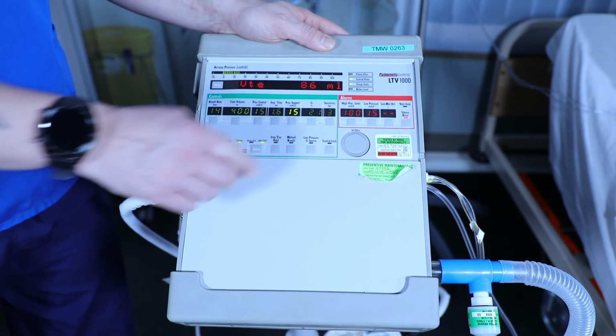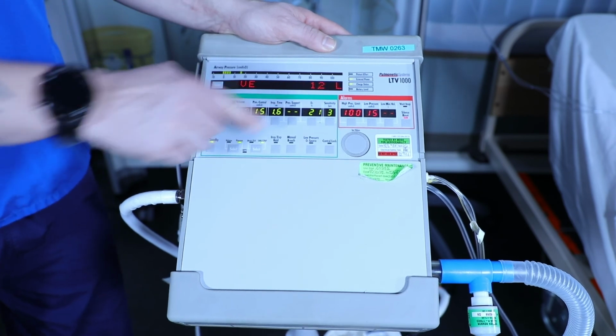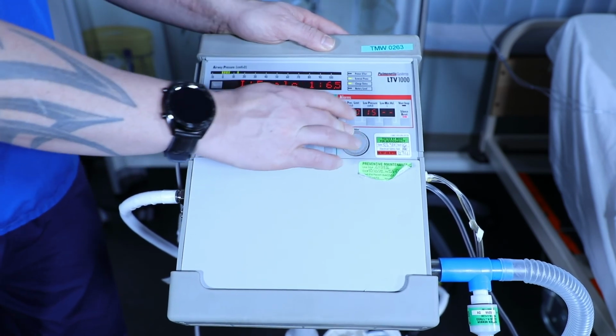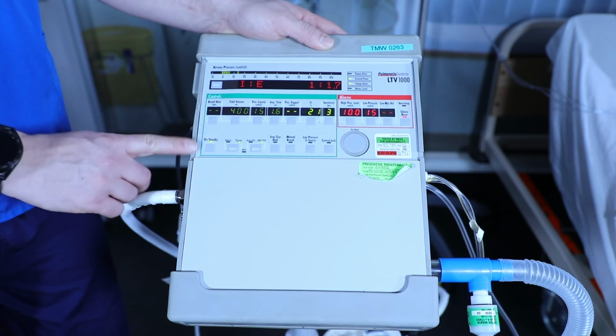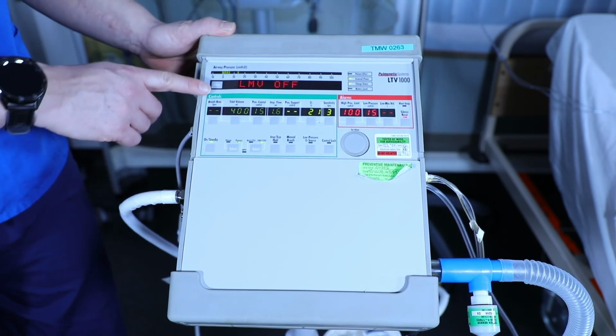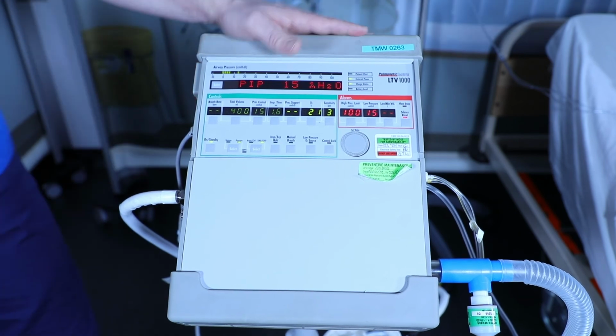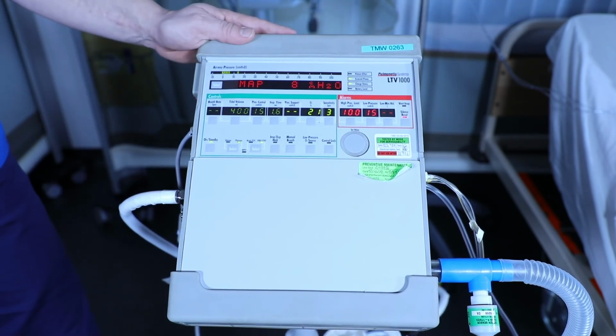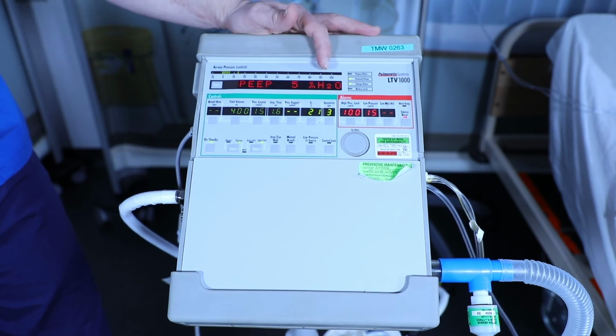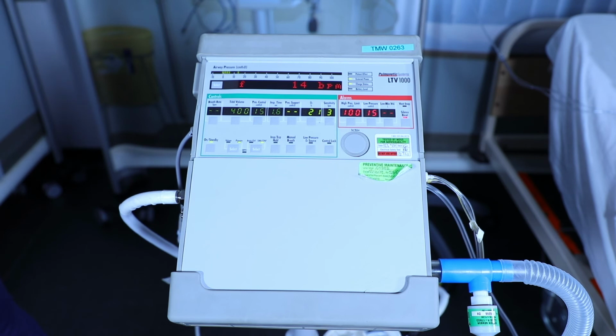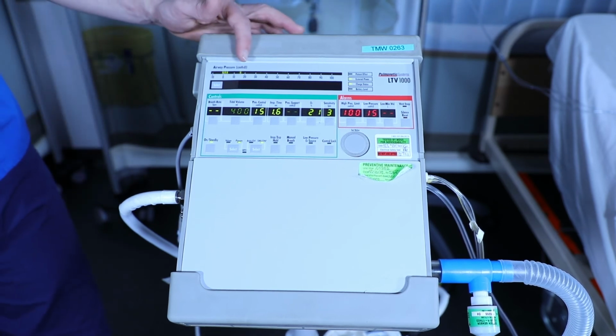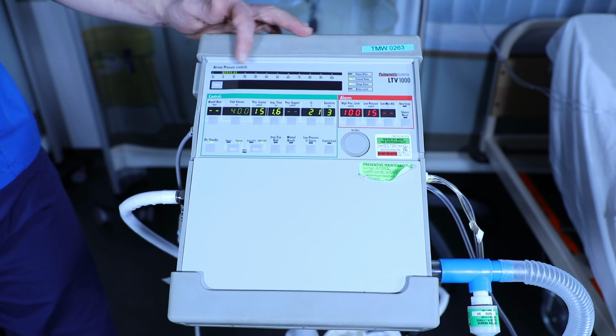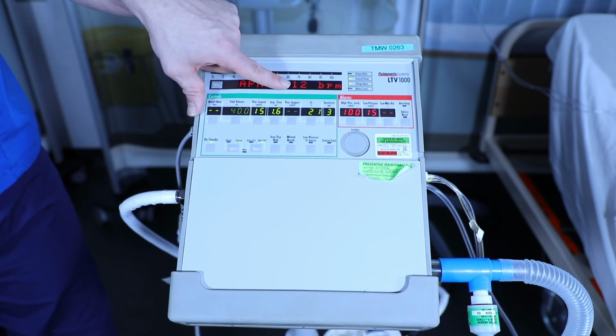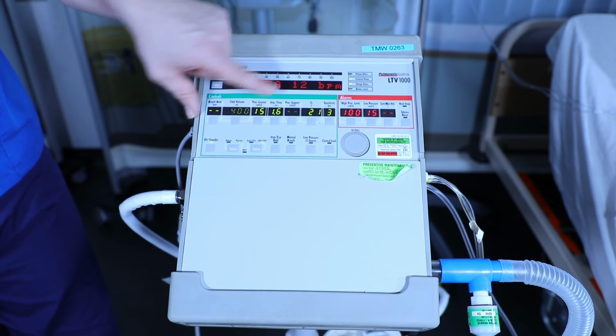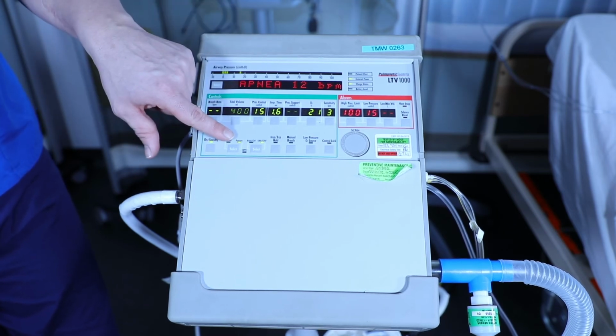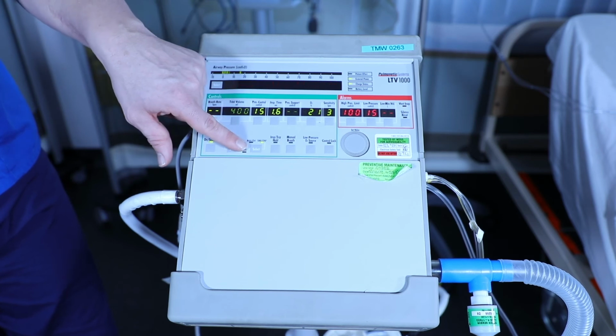We switch our pressures off, dash dash. The respiratory rate would be set to off, and now the patient will only the patient triggers the ventilator. In this scenario, our mannequin won't initiate any breaths, so after 20 seconds we should see our apnea alarm. 20 seconds have now passed. The ventilator defaults into apnea mode. The default breath rate is 12 breaths per minute, and the default mode will be the previous mode that we have set on the ventilator. In our case, it would have been pressure control SIMV.